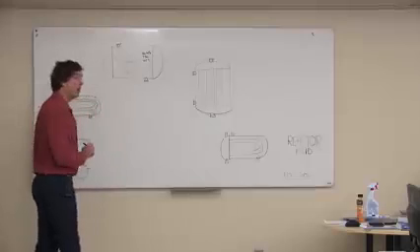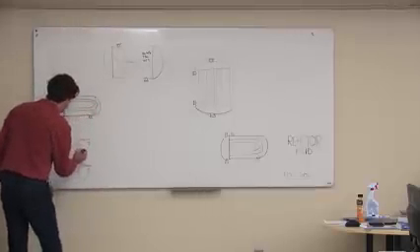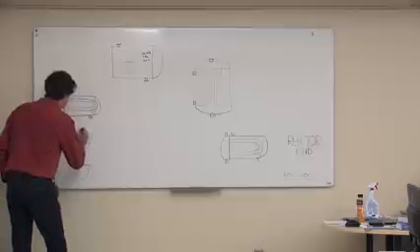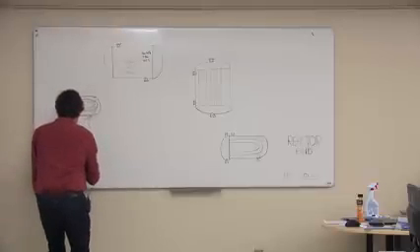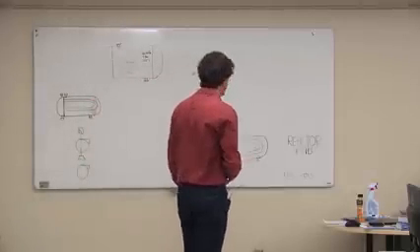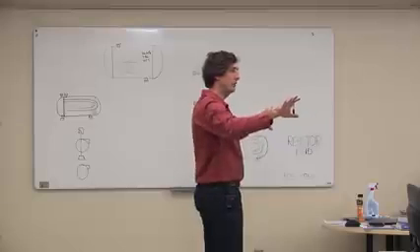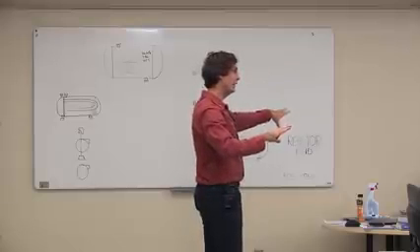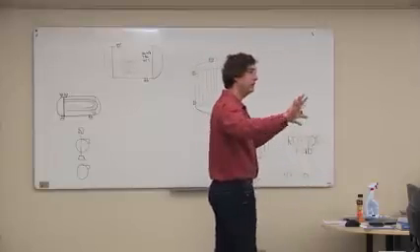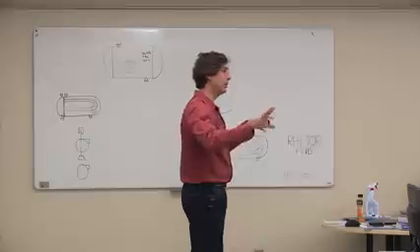So what we might want to do is have an electric motor, and we might also want to have a steam turbine to keep the pump running. So one pump with a shaft, electric motor on one side of the pump, and a steam turbine on the other side of the shaft. And maybe the steam system is a little bit more reliable than the electrical system.